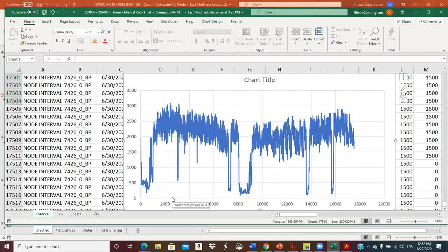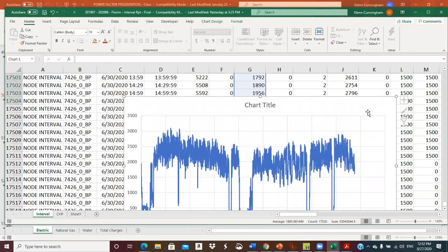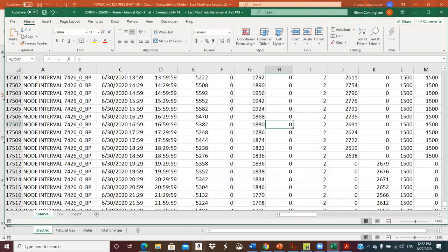And then you'd have to spread this out and look at it. But it looks like the kVAR is spending most of its time between 2,000 and 3,000. That big dip is when the plant is down for maintenance for 2 weeks. You see something like that. So anyway, if you're going to get in and do a serious study, you'd probably get an electrical engineer who has much more expertise than we would in something like that, and let them dig into this. Okay, enough of that.